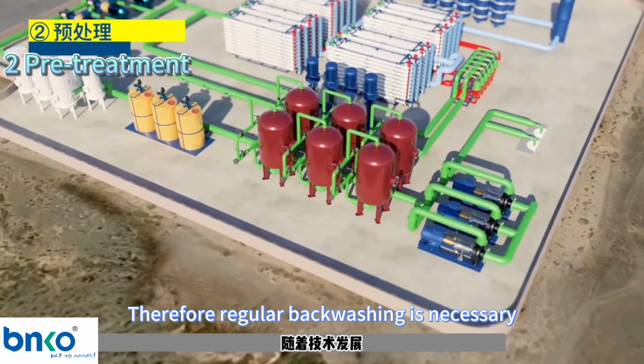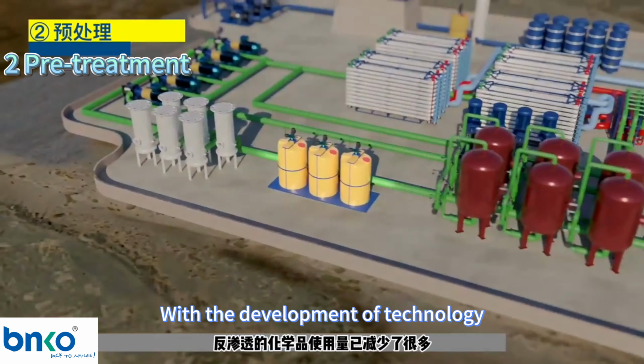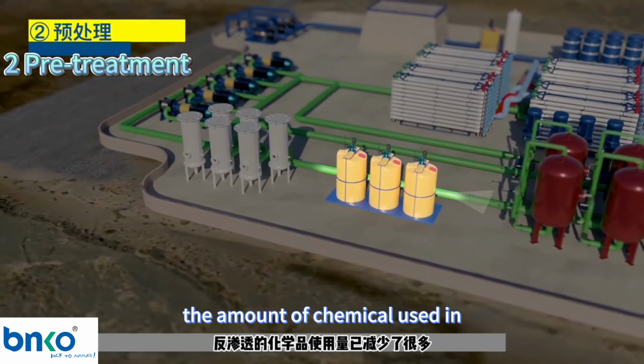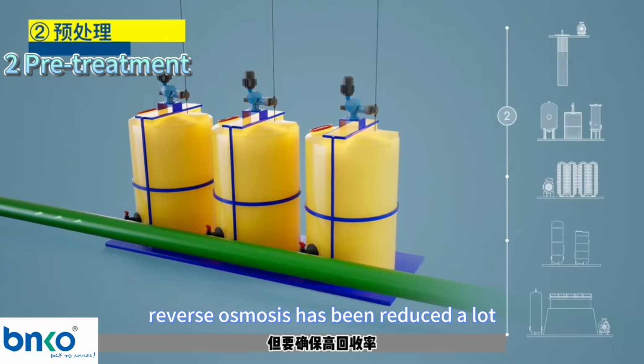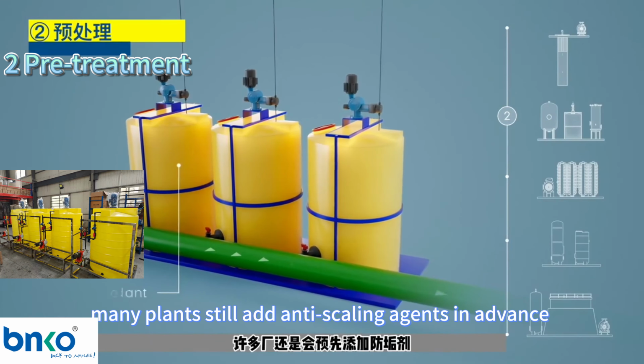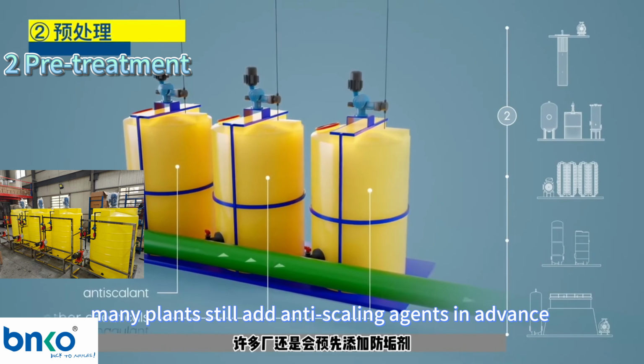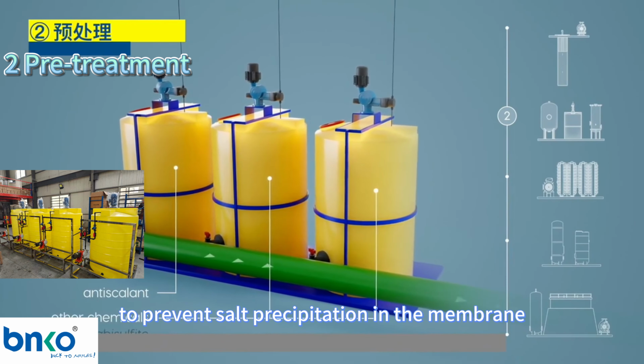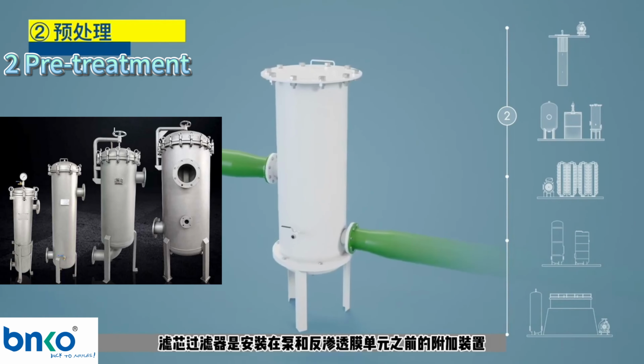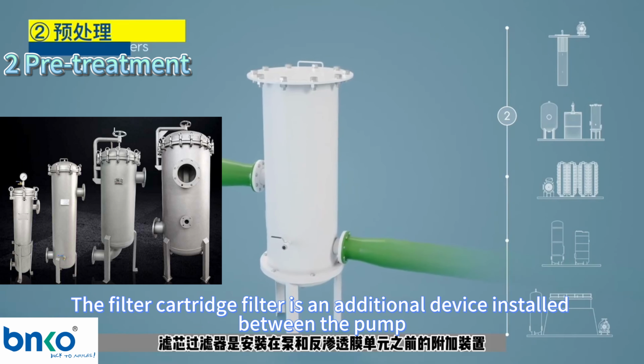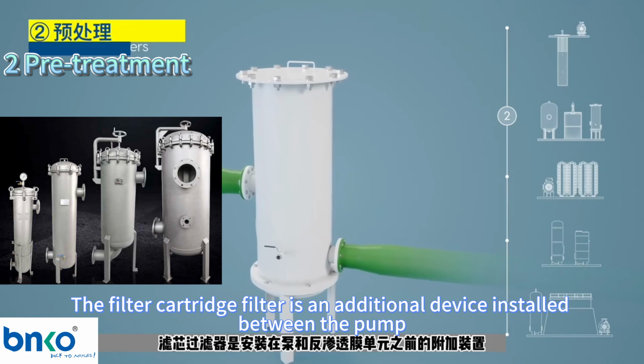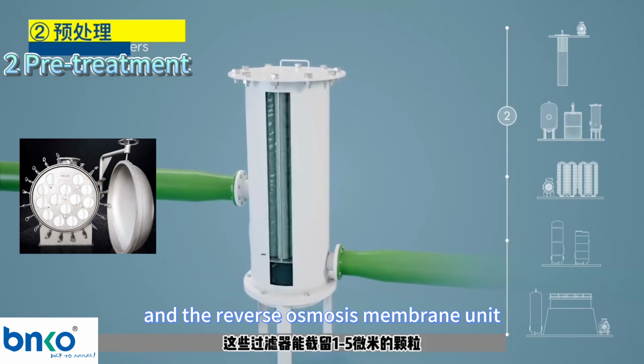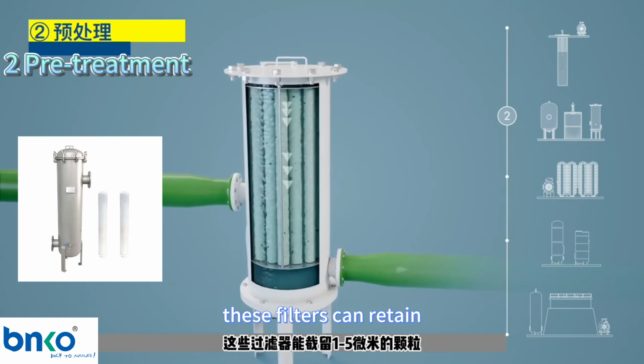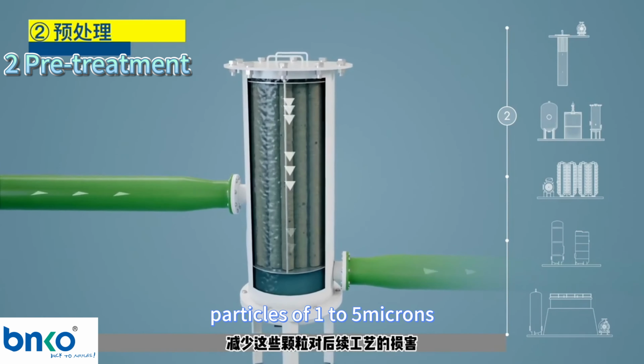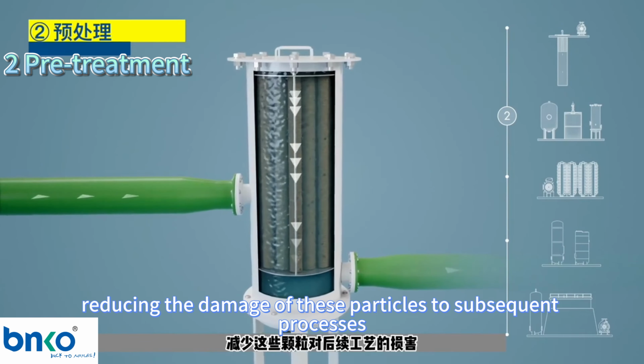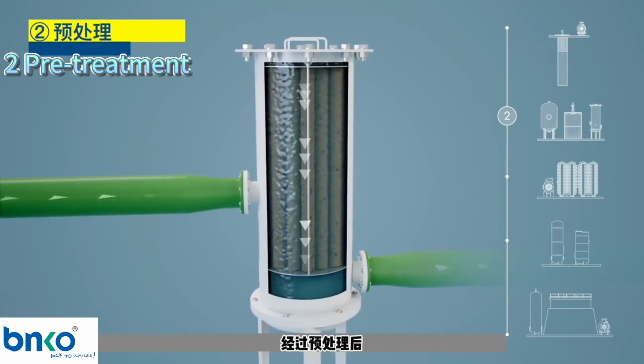With the development of technology, the amount of chemicals used in reverse osmosis has been reduced a lot, but to ensure improved recovery rates, many plants still add anti-scaling agents in advance to prevent salt precipitation in the membrane. The cartridge filter is an additional device installed between the pump and the reverse osmosis membrane unit. These filters can retain particles of 1 to 5 microns, reducing the damage of these particles to subsequent processes.